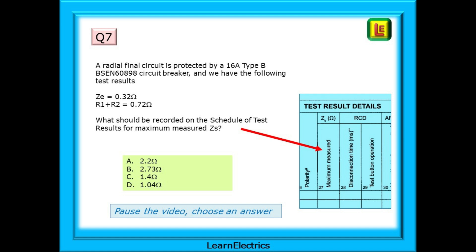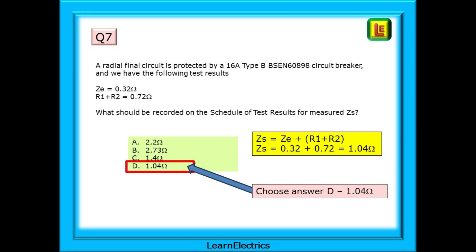ZS is equal to ZE plus R1 plus R2. So we have 0.32 plus 0.72 which is equal to 1.04 ohms. So choose answer D.